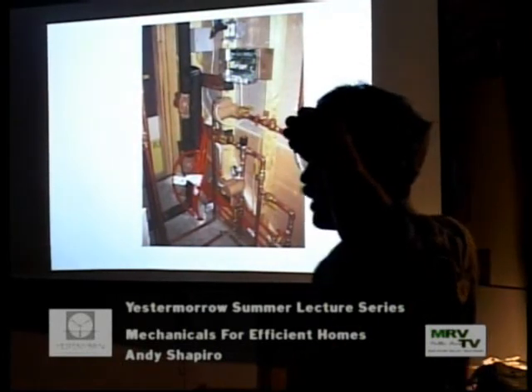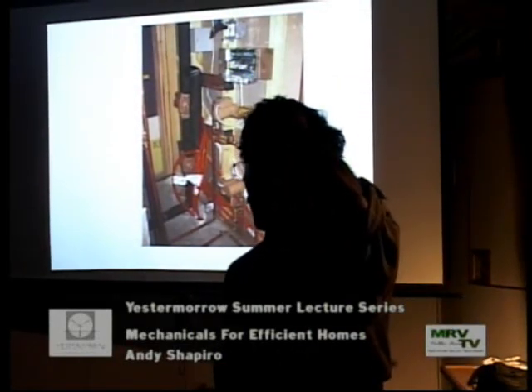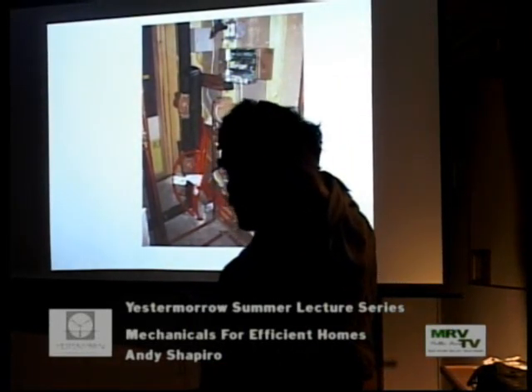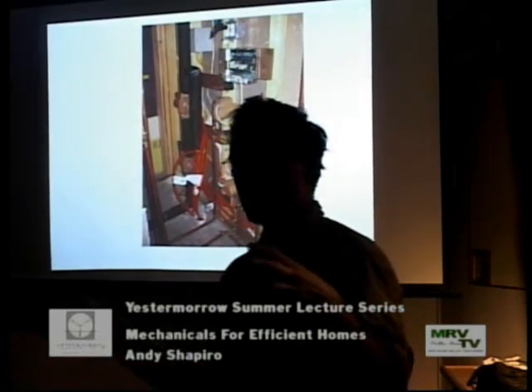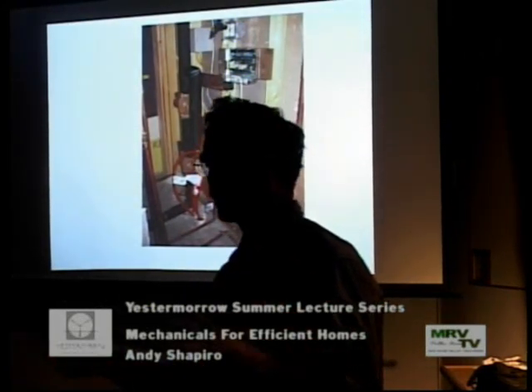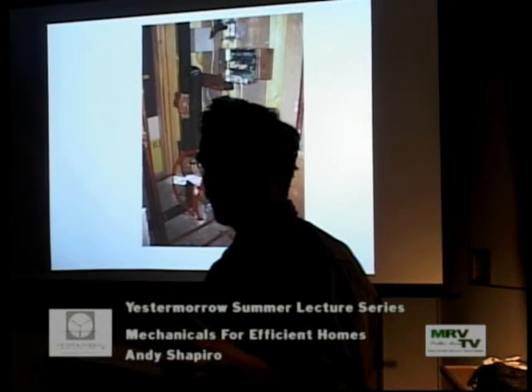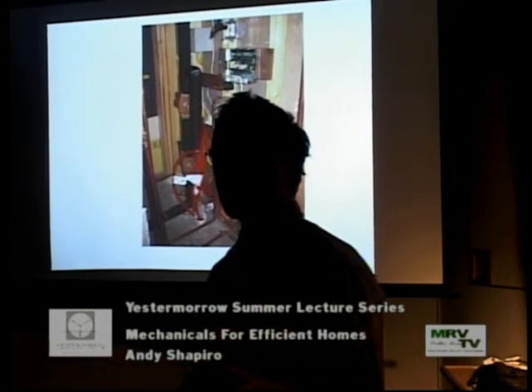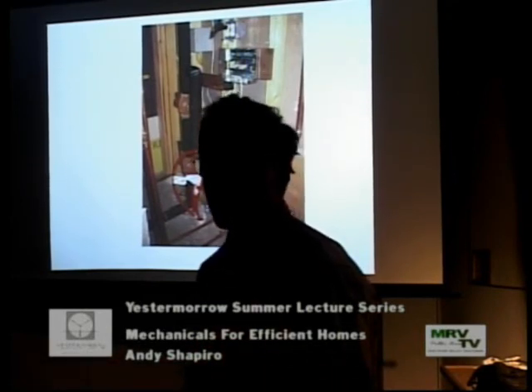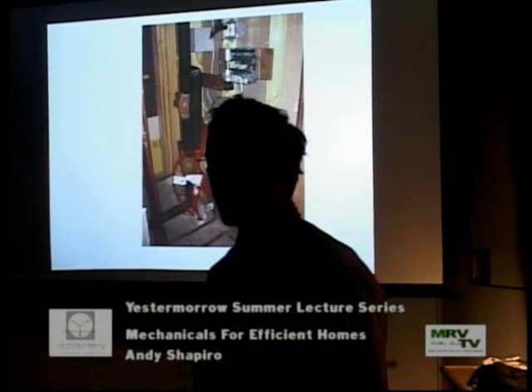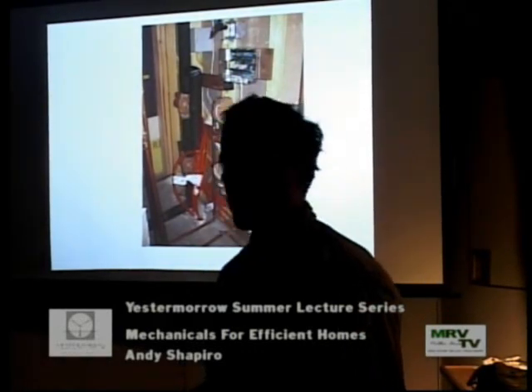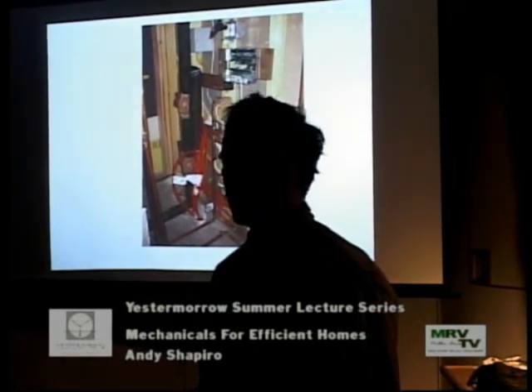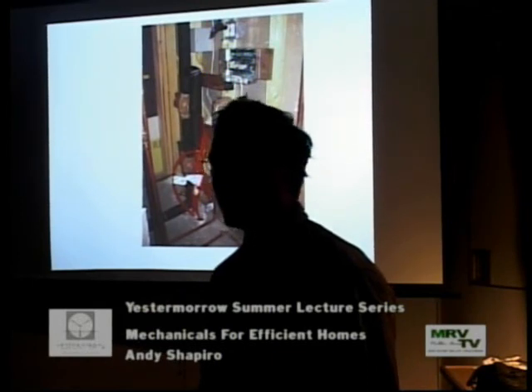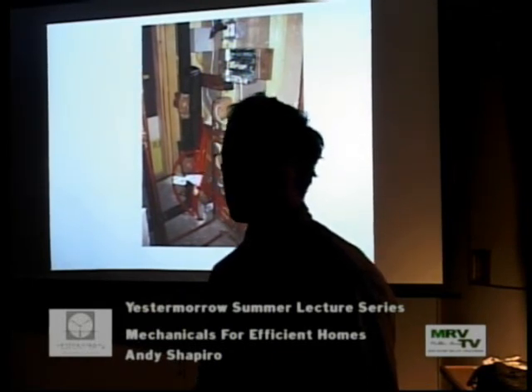I worked with Hilton Dyer on that, he did the PV stuff, he's very smart on all this. He said you can use a sealed combustion tank-type water heater that requires no electricity, and that's kind of the natural choice. I've used one of those in another off-grid house, but the problem is they're like 50% efficient, they're just dogs, and if they're using any hot water it's going to cost a lot to operate.